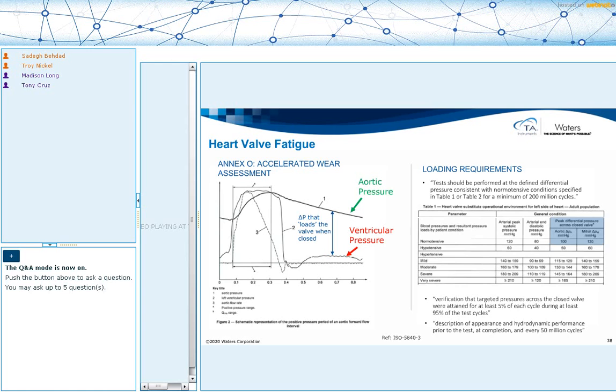So the standard states that you are going to test your valve for 200 million cycles and then look at the pressure differential. There are three things that you are going to look at. You are going to make sure that that pressure differential is achieved. So your pressure differential should go above 100 or 120, and it is maintained for 5% of the time of each cycle. And you have to make sure that that happens for at least 95% of your test cycles. This is the wear testing or fatigue testing. Every 50 million cycles, you have to stop the test and check your valve to measure the hydrodynamic aspect of it. You're looking at the appearance and at its leakage to see if it is affected after being exposed to fatigue.